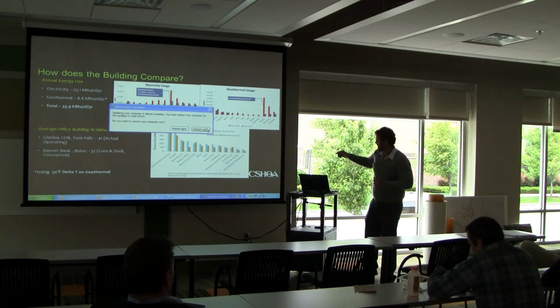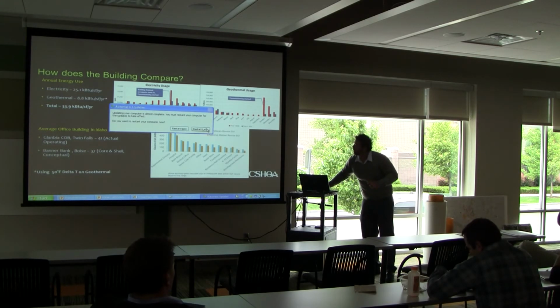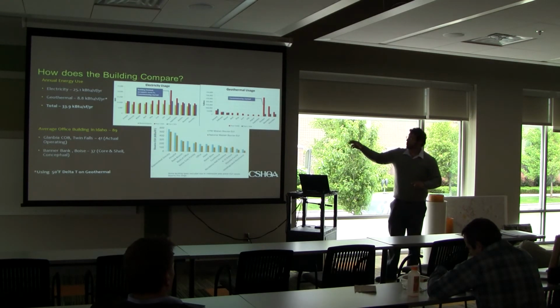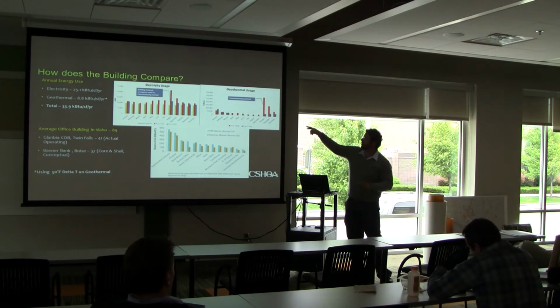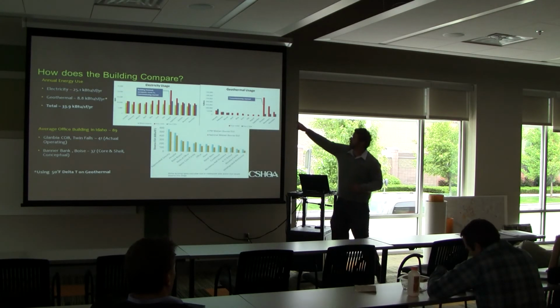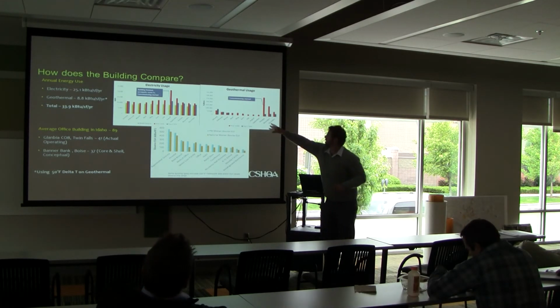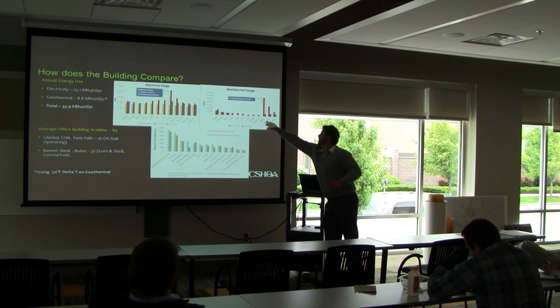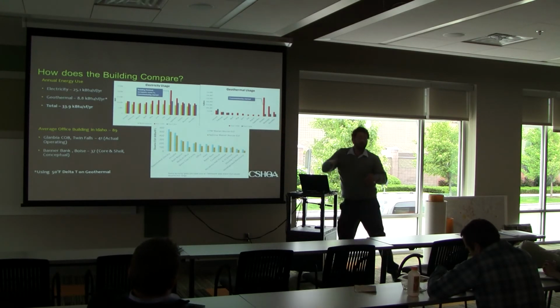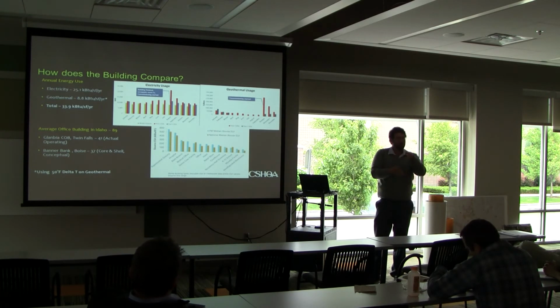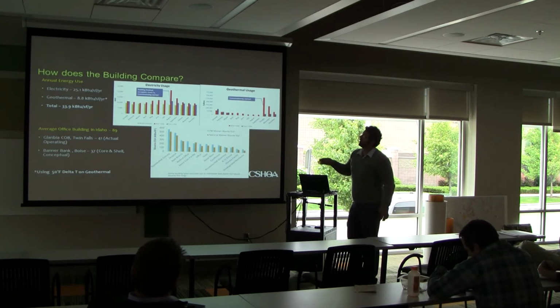So during commissioning, I worked with both Russ and the controls contractor to figure out a better valving technique. And as you can see, we're down, even a year later, this is year 2. It's a staged valve, so we still have the max valve for design day, but we have a much smaller valve which lets just a little bit of water in if we need to, specifically for domestic water.